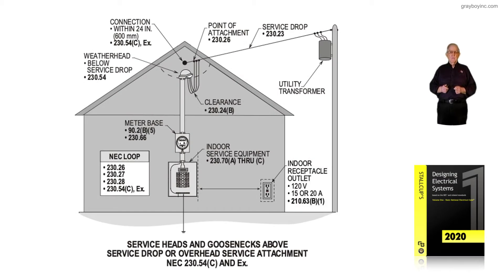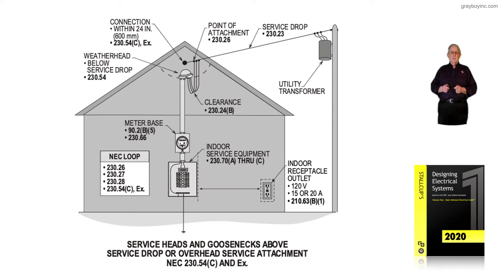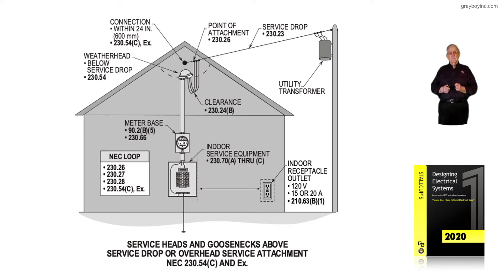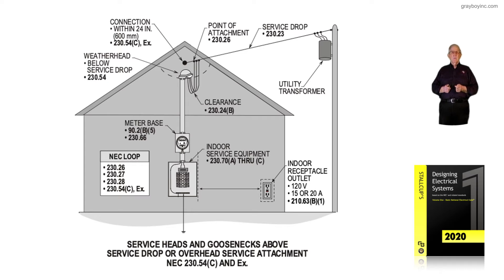This illustration deals with service heads and goosenecks above the service drop, or overhead service at the attachment, in accordance with NEC 230.54C and exception. Basically, this illustration is showing that the weatherhead is going to be located above or next to the point of attachment of the service drop — here it's located below — and notice it is permissible to be connected within 24 inches.